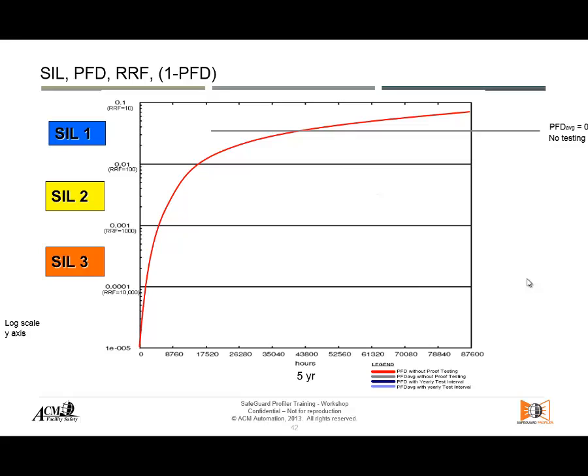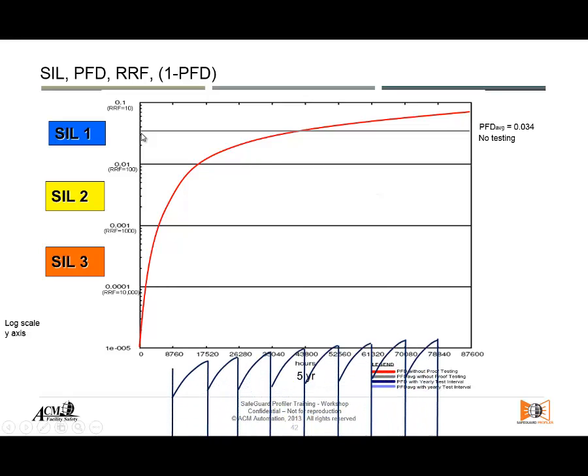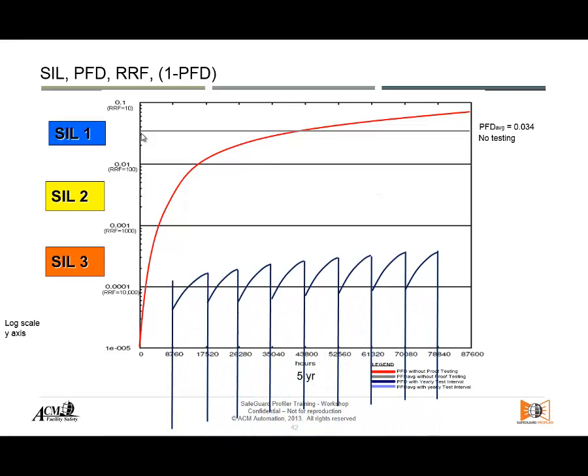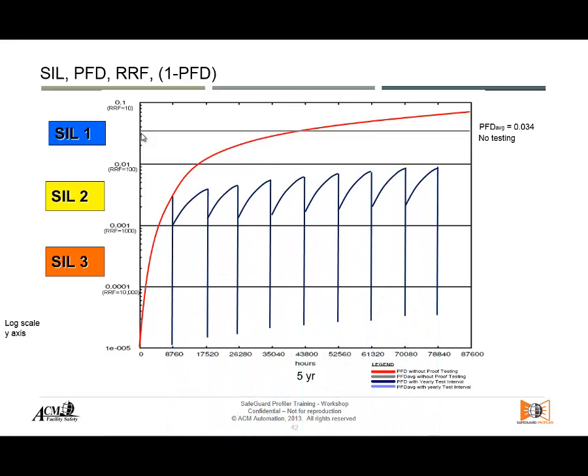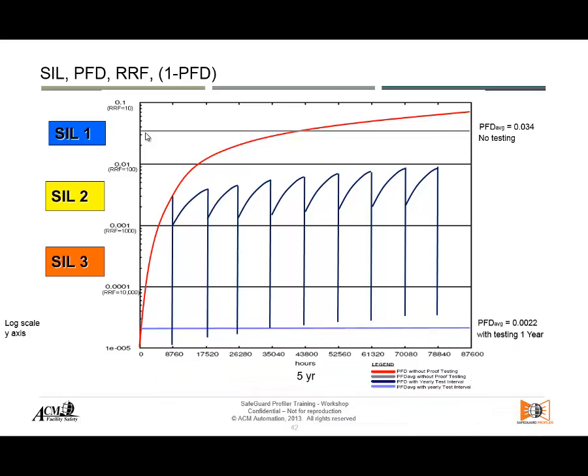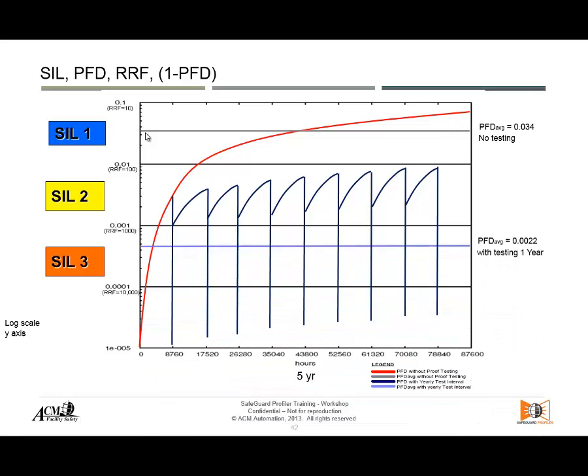Doing no tests at all — no testing — the probability of failure on demand would be, for example, 0.034. That would be corresponding to mid-SIL 1. And if we include proof testing, the probability of failure on demand will be reduced.